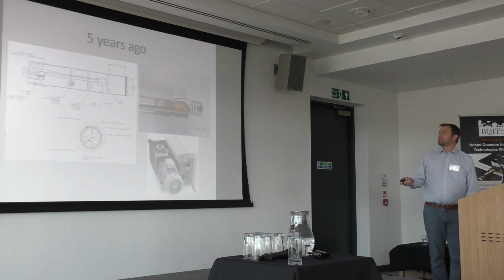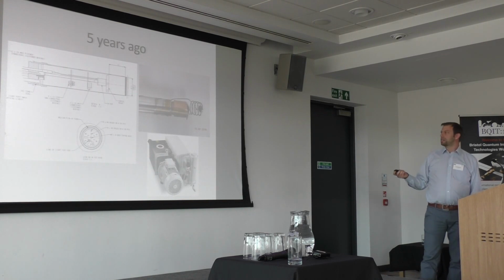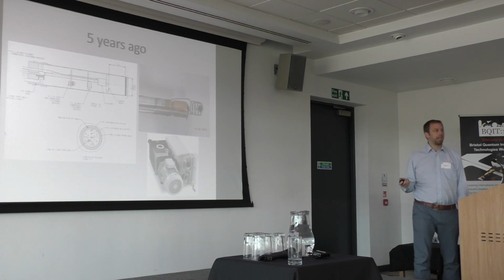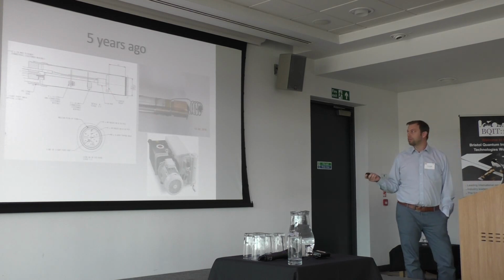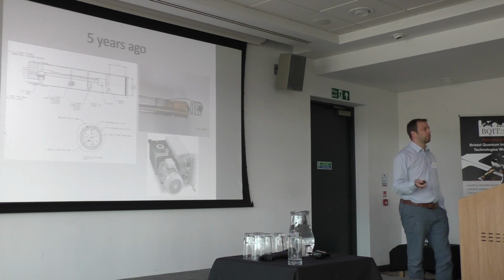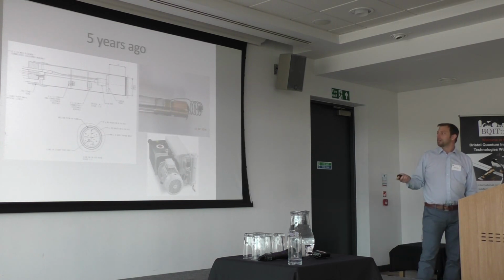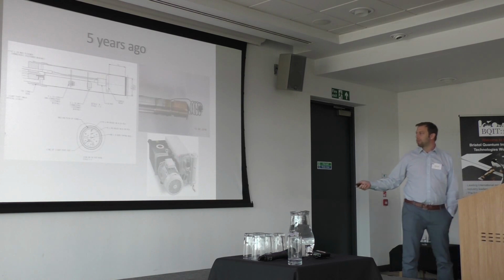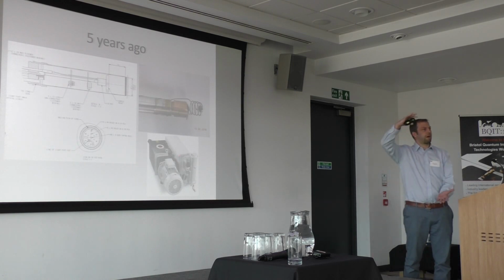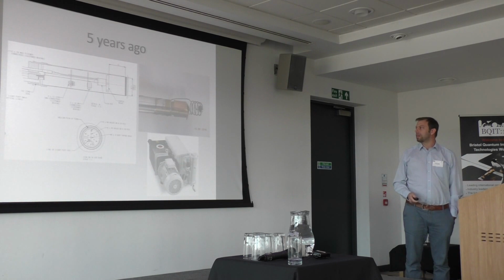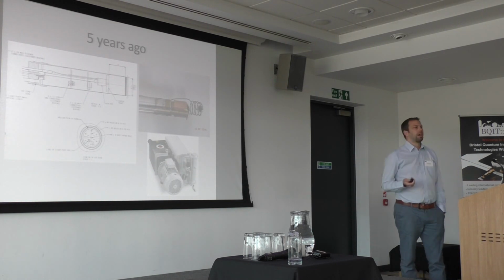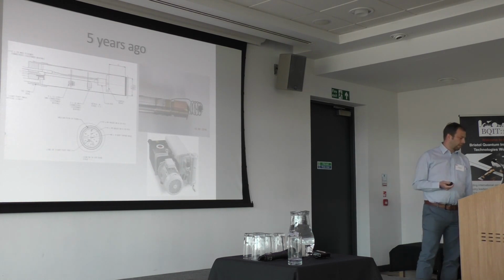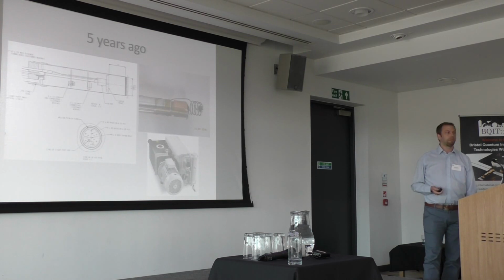As I said, 5 years ago no one was interested in these high cooling power 1K systems. We had just a very basic 1K pot with a very small pumping line — you'd flood your liquid helium-4 in there, pump on it, and get your sample down to 1.3 Kelvin to do some basic experiments. You'd have a small pump, only about this big, and that would be enough to do the job.